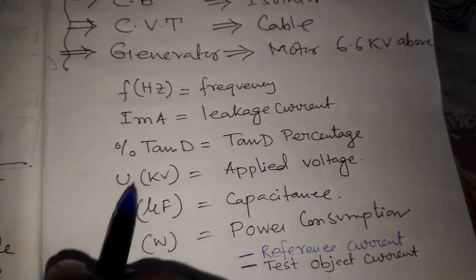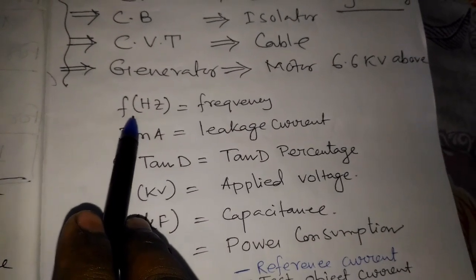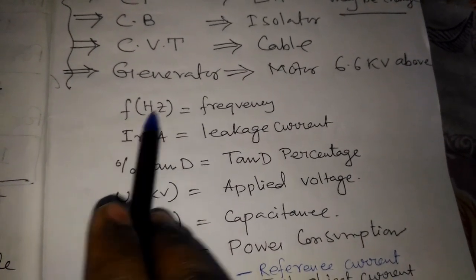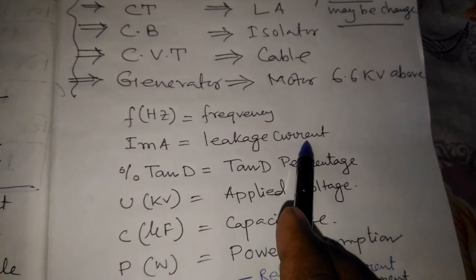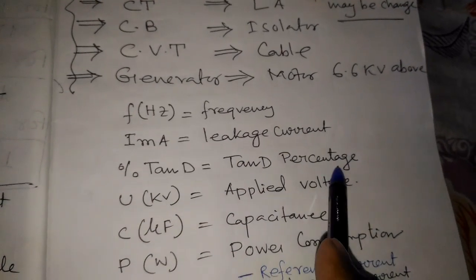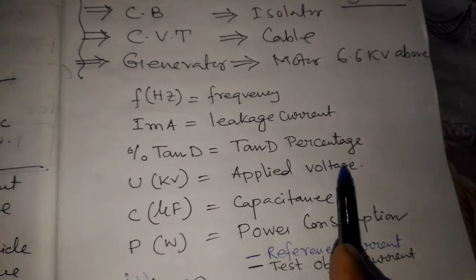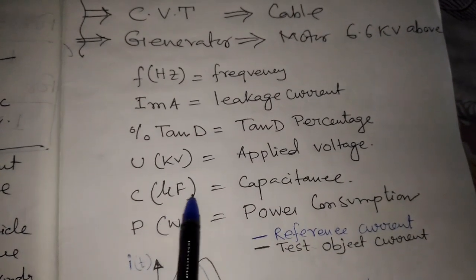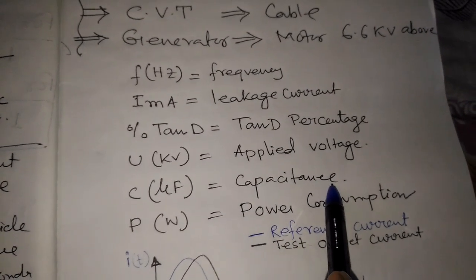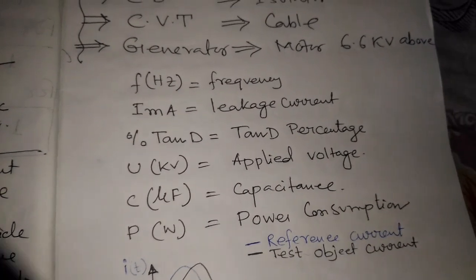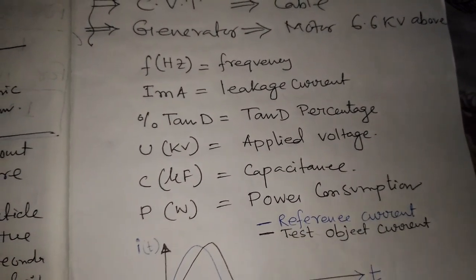After the Tan Delta test, using updated testing machines, we will get the following readings: the frequency applied, the leakage current flowing through the equipment, the Tan Delta percentage, the applied voltage to the terminal of the equipment under test, the capacitance C in microfarads between primary and secondary, and W — the power consumption.